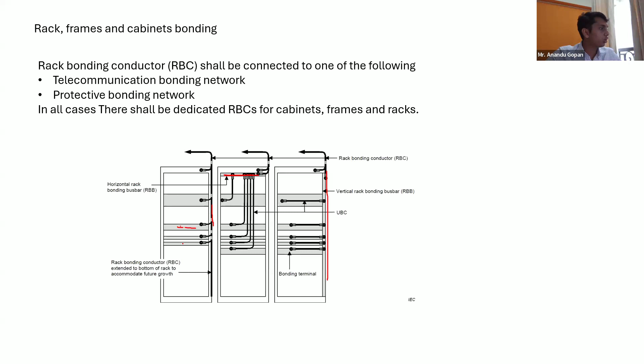The most important thing is, when you have a connection from this metallic point to this bar or to this conductor, whatever connections you follow, it should not be looped, such as going like this and then taking it outside. This is not allowed. You are supposed to individually earth them.